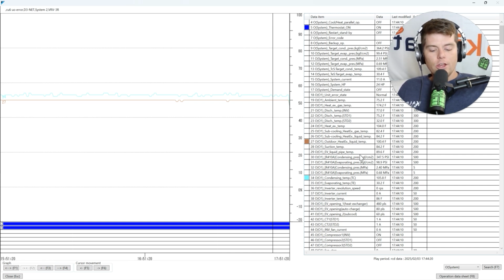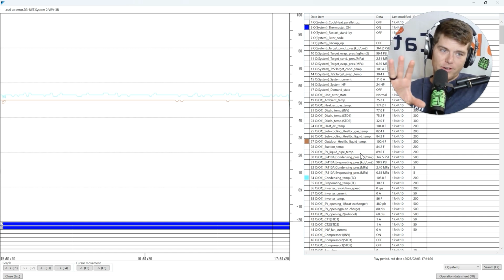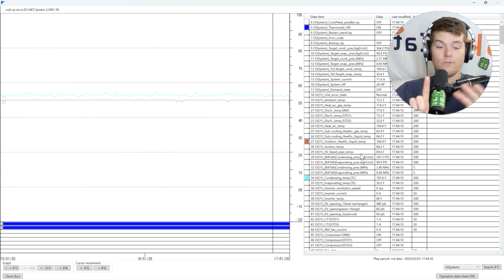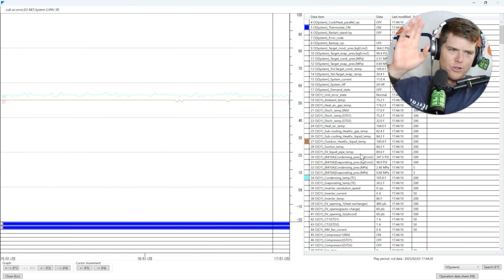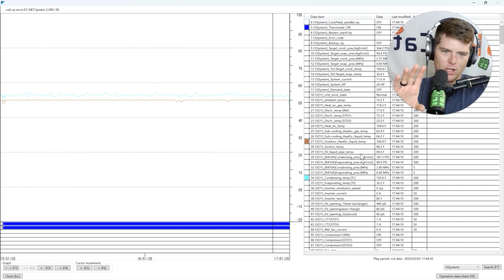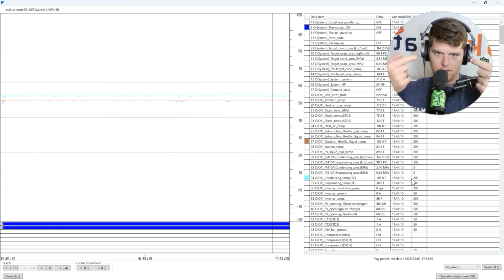But here's the thing. You would then turn around and ask yourself, okay, subcooling on the module, 5 degrees. Only using one coil when I should be using both coils because I have a 20-ton demand on the system. That's not great. Okay. I'll look past that. 5-degree subcooling on my master module. Okay. Now, the other ones are red flags, right? High suction superheat, high discharge superheat, red flag, red flag. Subcooling, 5 degrees, okay? Listen to me, look at me. Listen, 5 degree subcooling. What steps is your fan at?